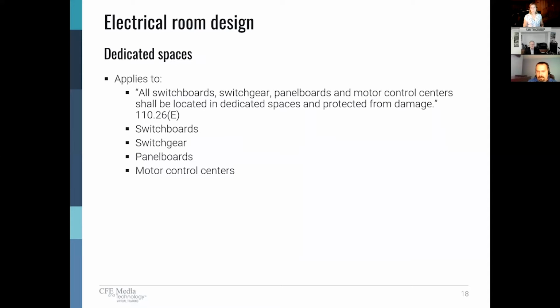So let's talk about dedicated spaces. This is distinct, as was shown in the diagram, from working spaces. It applies to all switchboards, switchgear, panelboards, and motor control centers, which shall be located in dedicated spaces and protected from damage. So we go to the next slide.